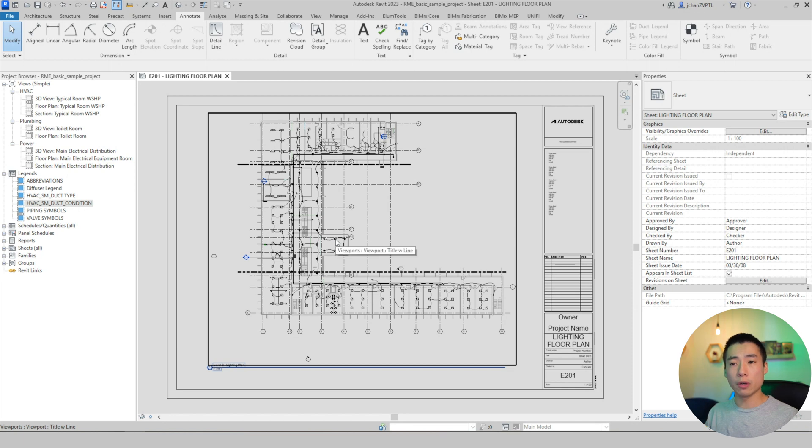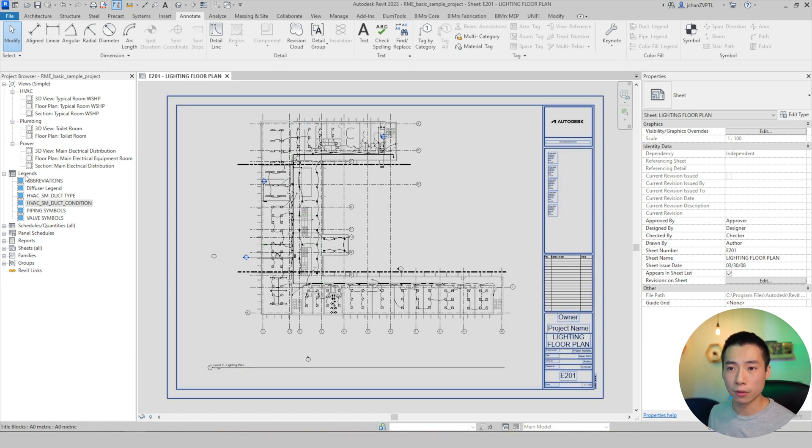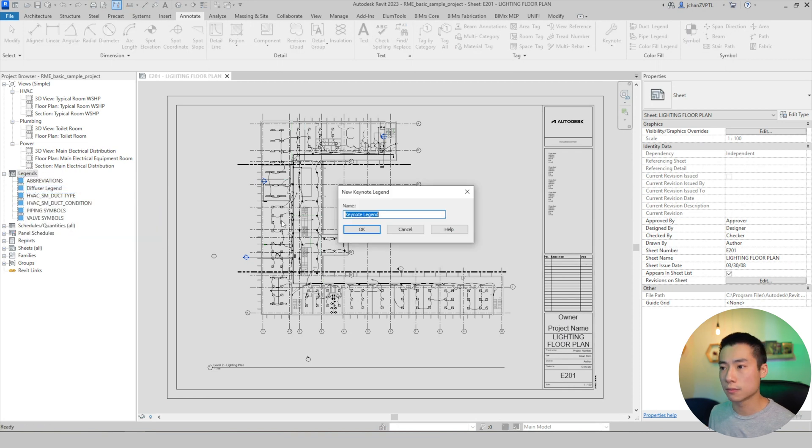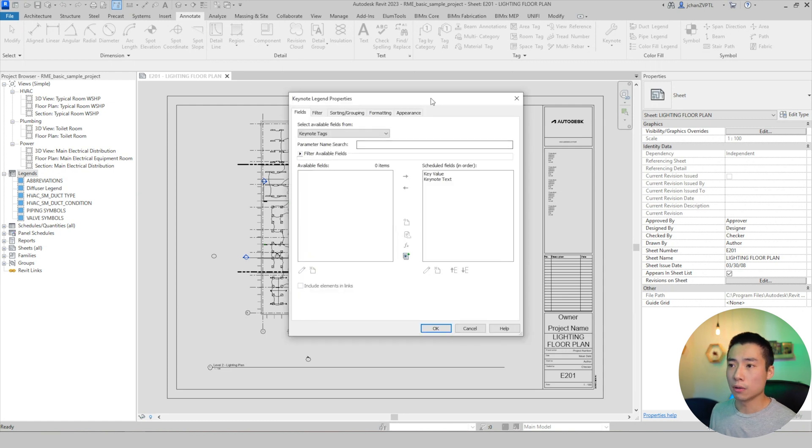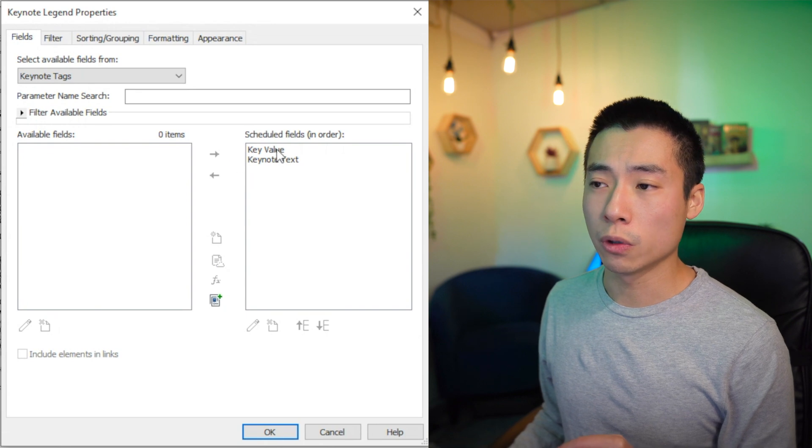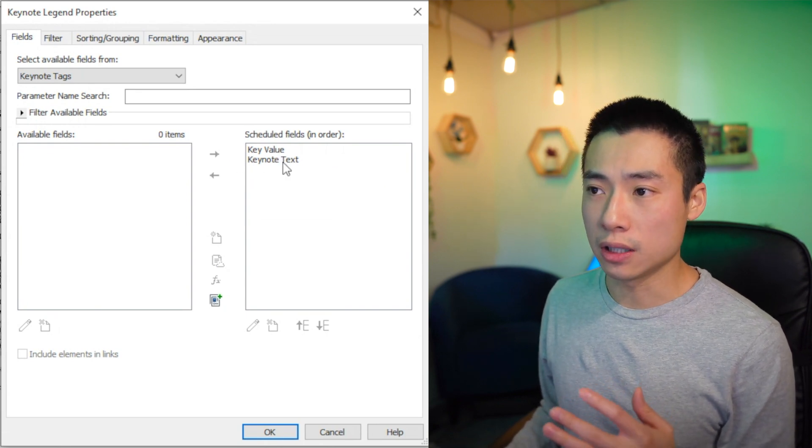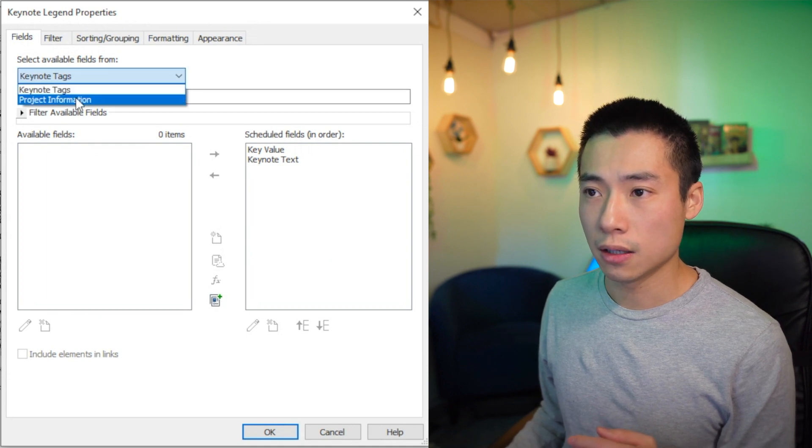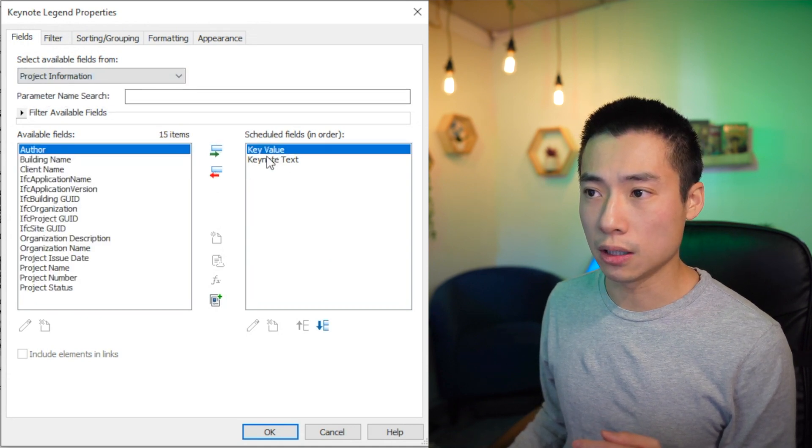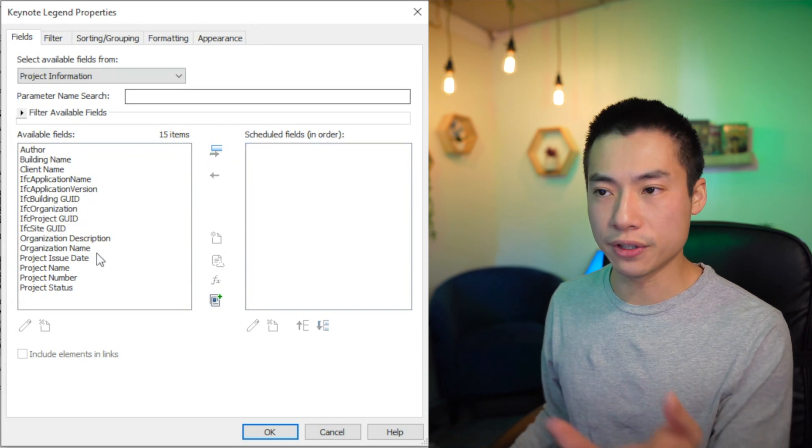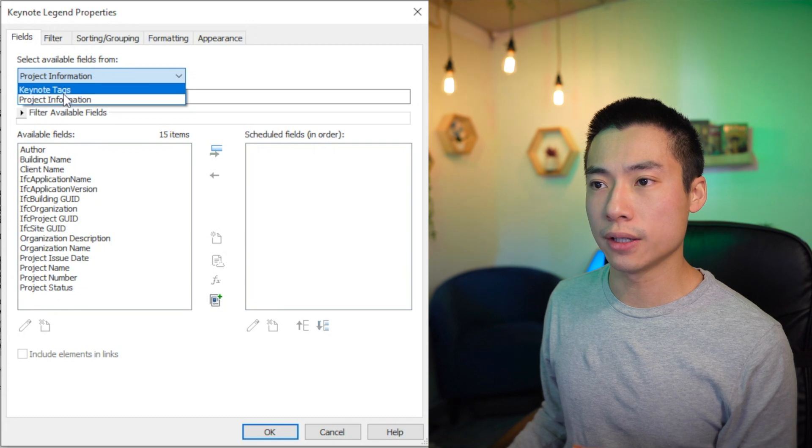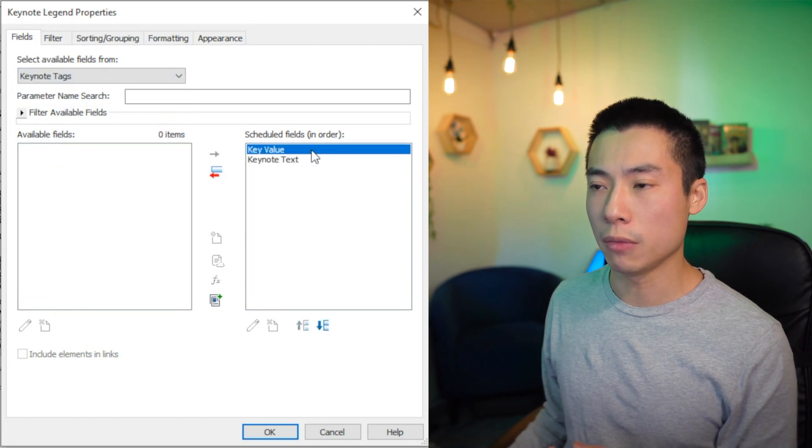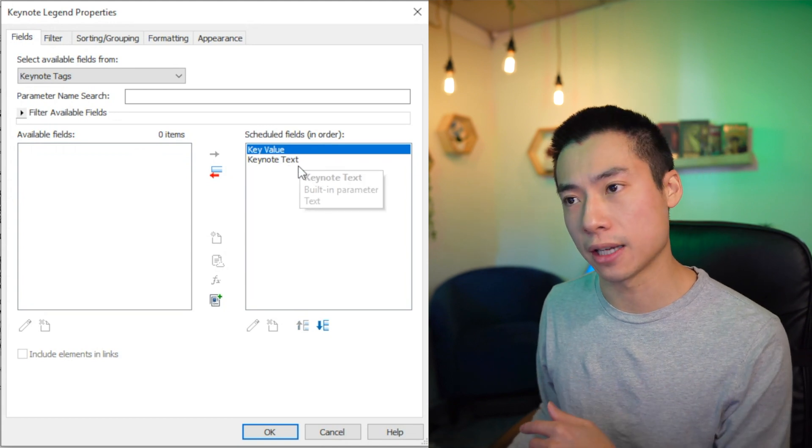And then step two is going to be to create your keynote legend. So over here under legend, you want to go ahead and right click. We're going to do a new keynote legend and then we're going to hit okay. So this brings up the keynote legend properties window. And from here, you want to just double check a couple of things. Your keynote value and text needs to be in this column over here. So if you don't see it, you might actually be here. We'll just reset this real quick. Let's say you're presented with like this window. So you want to go ahead and click on this, bring it to keynote tags, and then bring your two elements over. Make sure your keynote value is on the top and then your text is second.